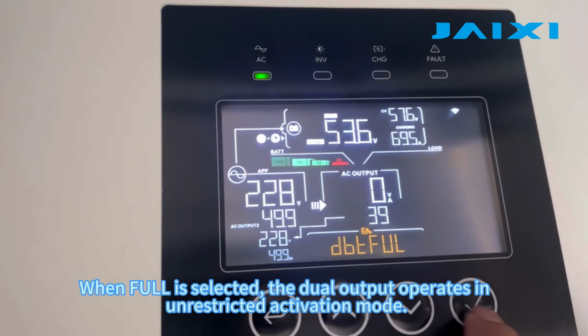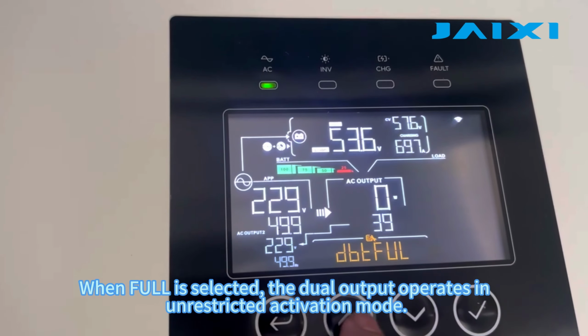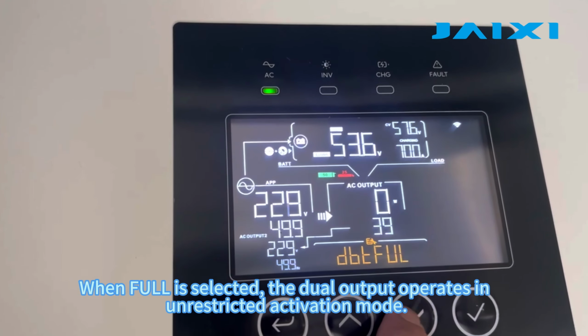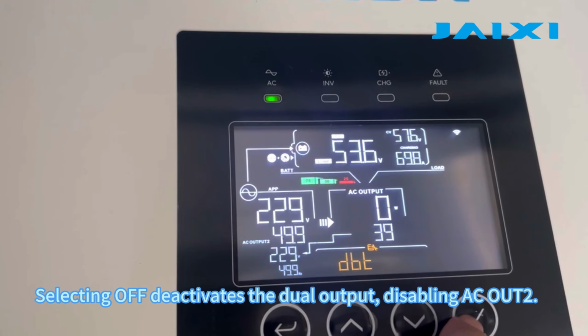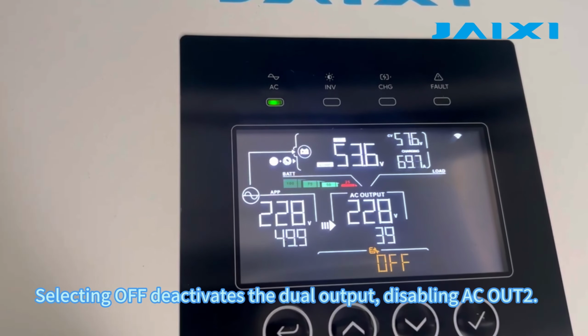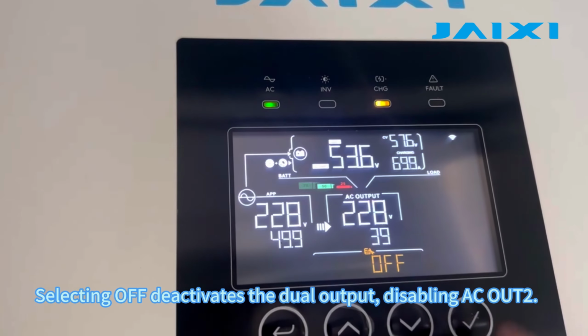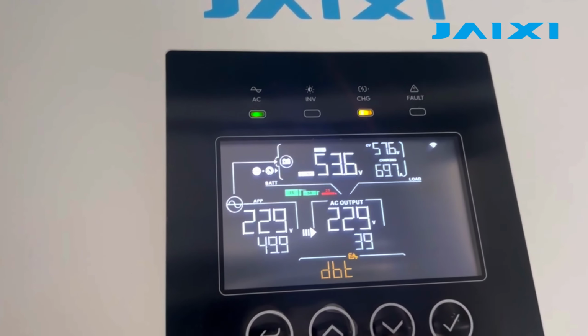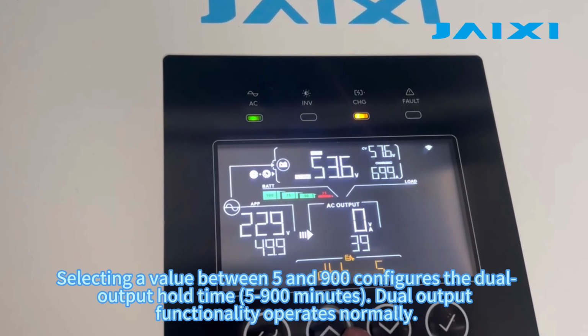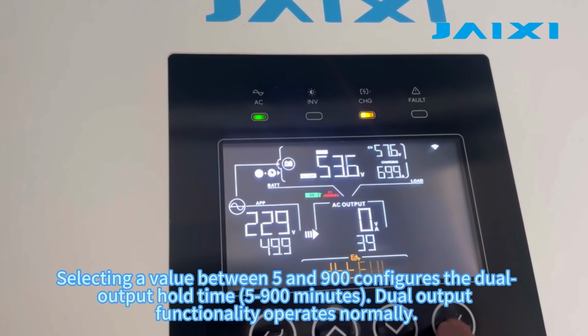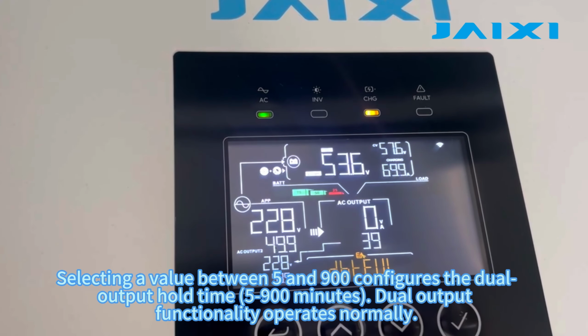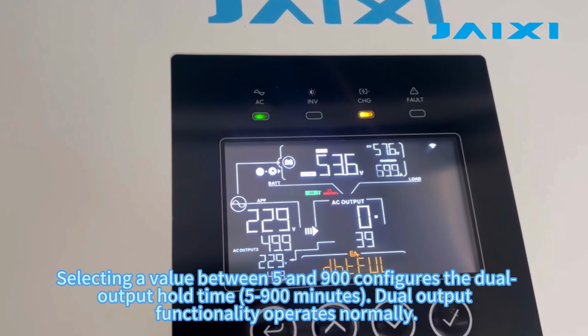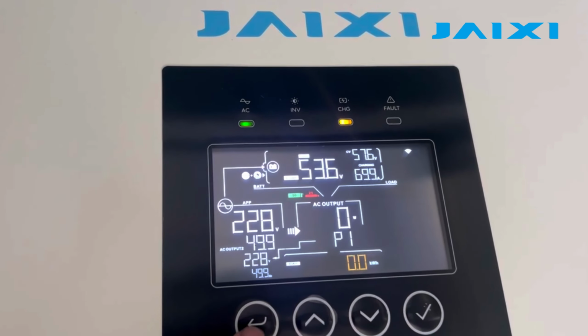When full is selected, the dual output operates in unrestricted activation mode. Selecting off deactivates the dual output, disabling AC out 2. Selecting a value between 5 and 900 configures the dual output hold time to 5 to 900 minutes. Dual output functionality operates normally.